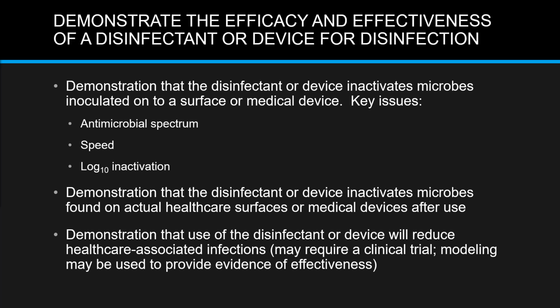The key thing for the disinfectant or the device is the antimicrobial spectrum. What does it kill? Obviously, for vaginal and rectal probes, it must disinfect things such as gonorrhea, syphilis, HIV, sexually transmitted agents, but certainly also HPV. The speed: how quickly does it work? We want a disinfectant or a device to work in seconds or at most a few minutes. We don't want disinfectants and devices to take minutes to hours to work. And then how many logs does it kill, which is part of the definition of high-level disinfection.